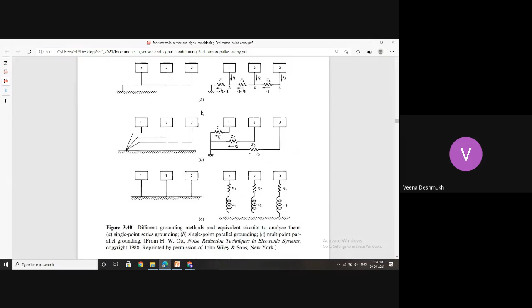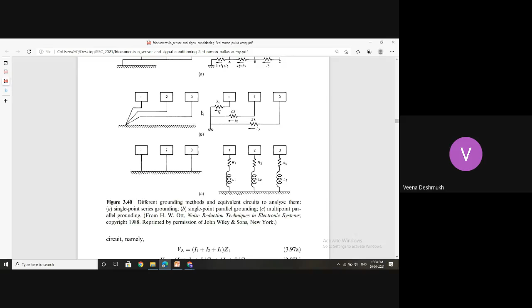In the third type, what do we have? Multiple points connected in parallel to ground. So parallelly they are connected to ground. Here, individual impedances like this are connected to different points, but all of them are grounded. Now what is happening here? There is a slight difference between this connection and this connection. For us, when we assume that short always means zero resistance, all these three connections look similar, or rather the same. But in practice, if the wires or the leads are too long, they contribute to the impedance, so these considerations have to be made.